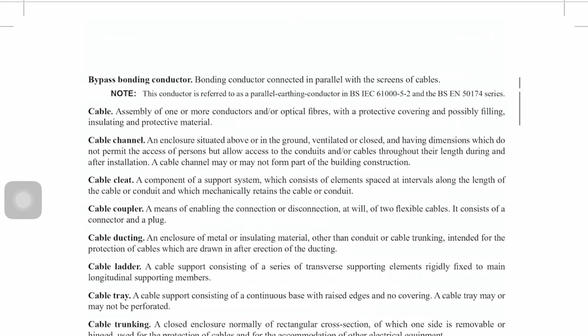Another one that I really do like to labour is CPC. Most people call it an earth wire, but it isn't - it's a protective conductor, one of the four protective conductors you need to be familiar with. So you've got earthing conductor, CPC - circuit protective conductor, main protective bonding conductor, and supplementary protective bonding conductor. You need to be familiar with those, and I'm going to show you a picture before we finish this session.